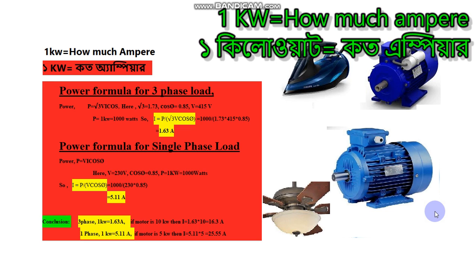The first is the power formula for a three-phase load, and the second is the power formula for a single-phase load. The power formula for a three-phase load is: P = √3 × V × I × cosθ. Here, √3 is equal to 1.73, cosθ (power factor) is equal to 0.85, V is equal to 415 volts, and let's take power P equal to 1 kilowatt, which is 1000 watts.